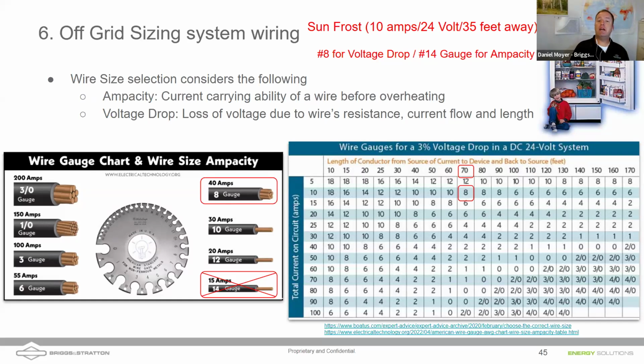10 amps, great, let's go ahead and get 15 gauge or 14 gauge wire. 14 gauge wire can handle 15 amps, no problem. But when we realize we're only operating at 24 volts, there's not a lot of pressure going through those wires. We're going to need a bigger pipe, or bigger conductor, to allow that energy to flow with less pressure. So looking at this voltage drop table, we understand we actually need 8 gauge wire. That's probably part of why we moved away from that DC architecture, and now we just run the entire home on AC instead.